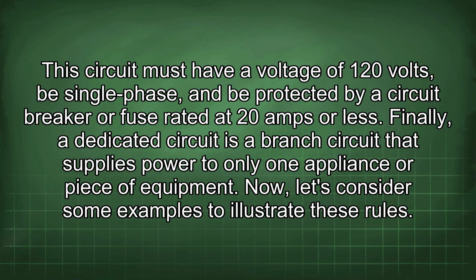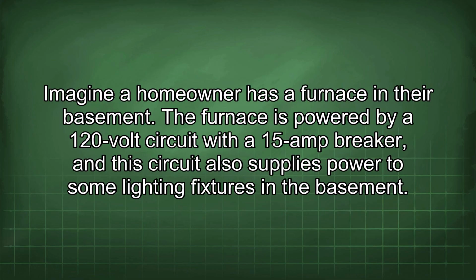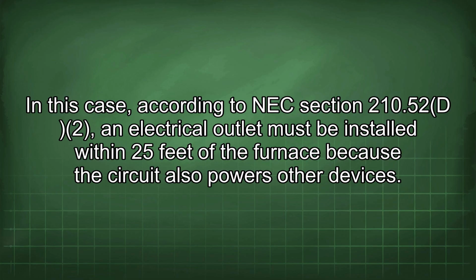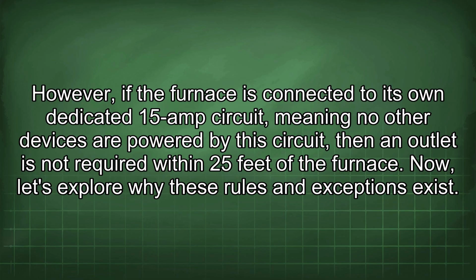Now, let's consider some examples to illustrate these rules. Imagine a homeowner has a furnace in their basement. The furnace is powered by a 120-volt circuit with a 15-amp breaker, and the circuit also supplies power to some lighting fixtures in the basement. In this case, according to NEC Section 210.52(D)(2), an electrical outlet must be installed within 25 feet of the furnace because the circuit also powers other devices. However, if the furnace is connected to its own dedicated 15-amp circuit, meaning no other devices are powered by the circuit, then an outlet is not required within 25 feet of the furnace.